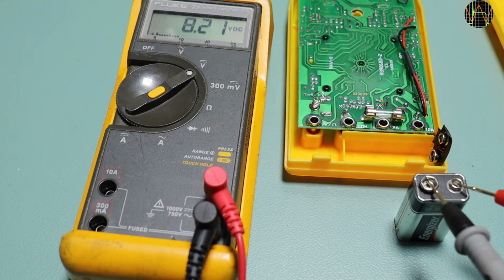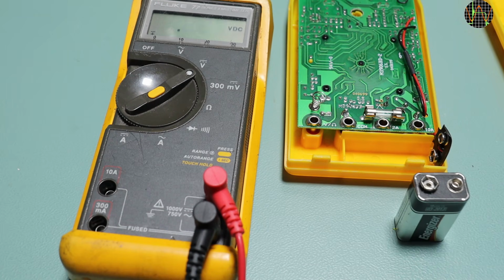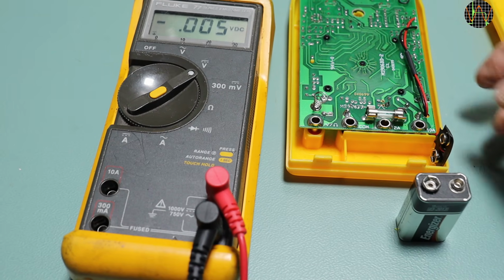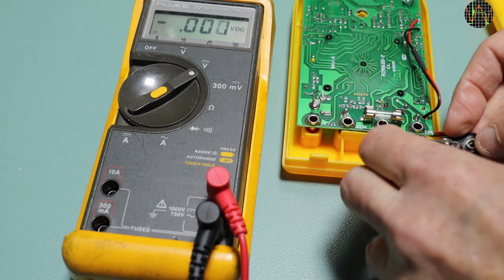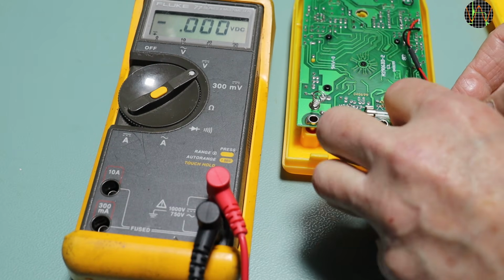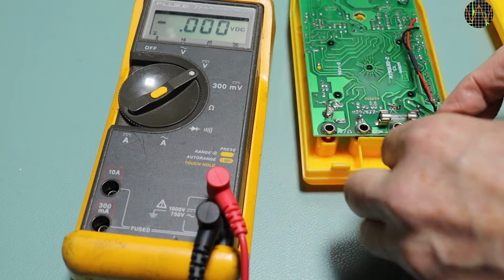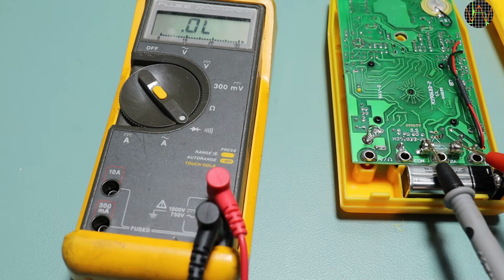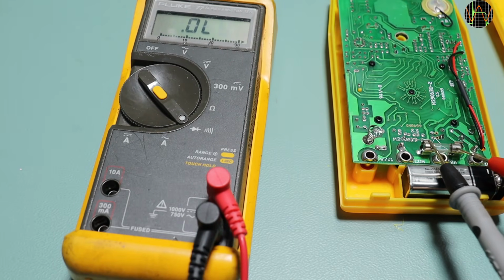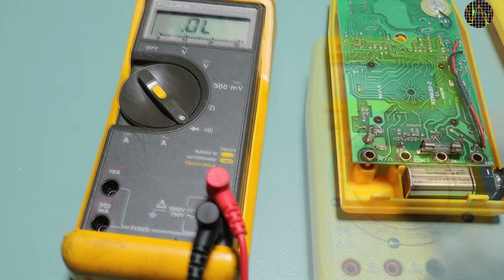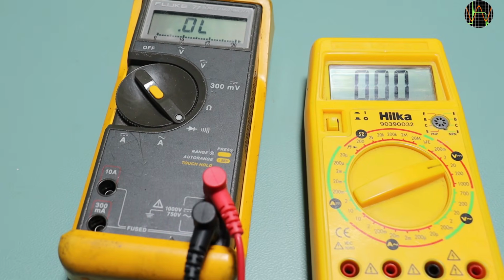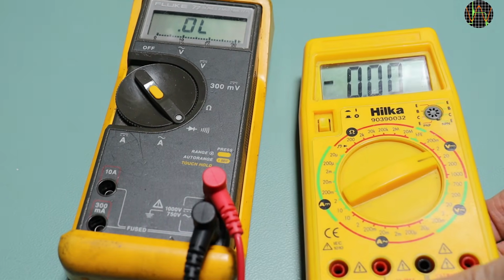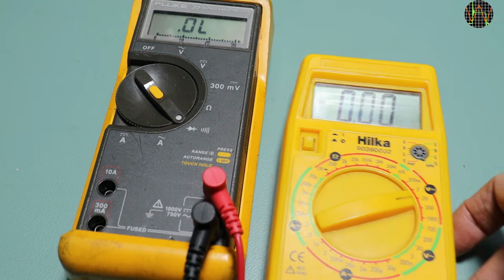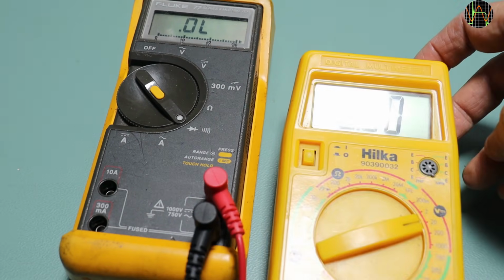To see if I need to worry which one is for what, I need to test the meter to see if it needs calibrating. For convenience, I use a not new but still reasonably fresh replacement battery. And while we're at it, a quick test of the 2 amp fuse reveals that it's still okay. With a replacement battery, the meter turns on. It has a relatively large display, easy to read. Apologies for the glare of the overhead lights.